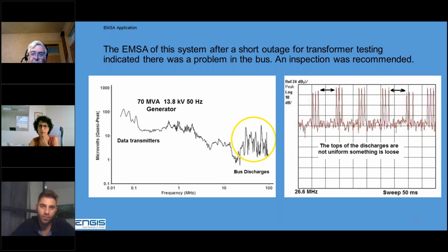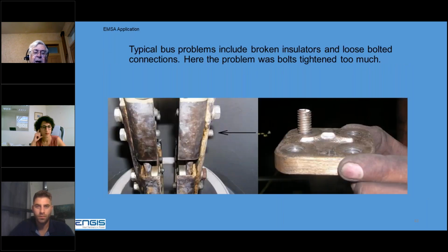Something is moving. So we recommended an inspection for the bus, and they were able to come down, I think 2 weeks later, and look at it. Usually the problem with the bus is broken insulators and loose bolted connections. In this case, they tightened the bolts too much and they snapped the heads off, or snapped the bolt in two, and they left it. All it took was to say, hey, we need new bolts, and take it out and put new bolts in. But they didn't, they left it that way. So that bus would have failed, and they did not know they had a bolting problem till we did the EMSA testing.